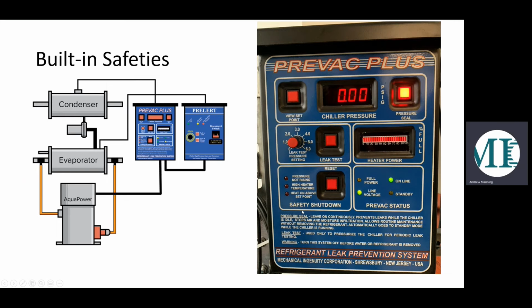We do have some safety shutdown measures built in. So the first is pressure not rising. That's a timing circuit. So in the pressure seal mode we just talked about, if the system doesn't bring the machine up to pressure in 4 hours, it shuts down. That means something's wrong. It should be brought into equilibrium by that 4-hour mark. And for the leak test mode, it's going to shut down after 8 hours, just because that's the typical length of a shift, and the leak test should be completed by then.